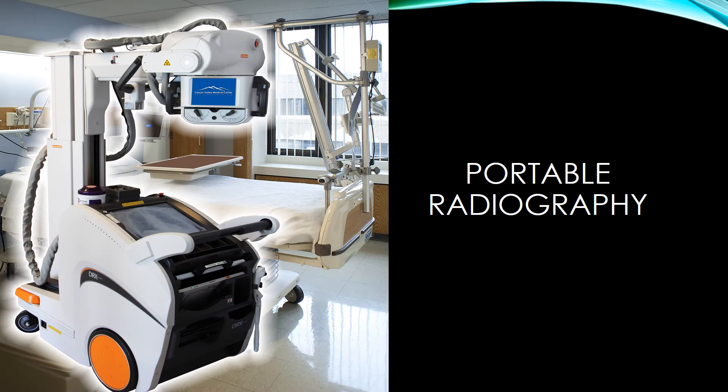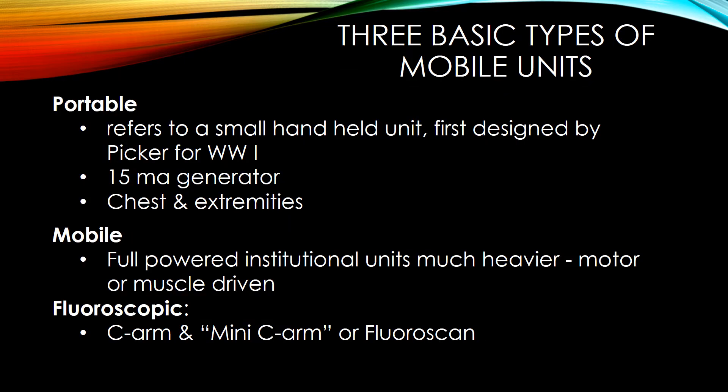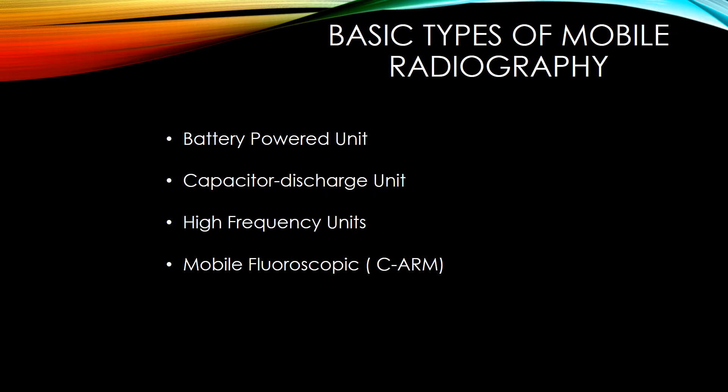Portable radiography. There are three basic types of mobile units. Portable refers to a small handheld unit first designed by Picker for World War I — it had a 15 mA generator and was used for chest and extremities in the field. Mobile refers to a full-powered institutional unit, much heavier and motor or muscle driven. Fluoroscopic refers to a C-arm, mini C-arm, or fluoroscan. Basic types include battery-powered units, capacitor discharge units, high frequency units, and mobile fluoroscopic or C-arm units.